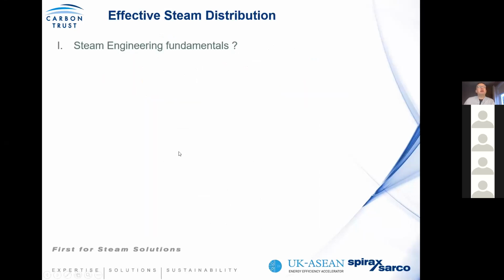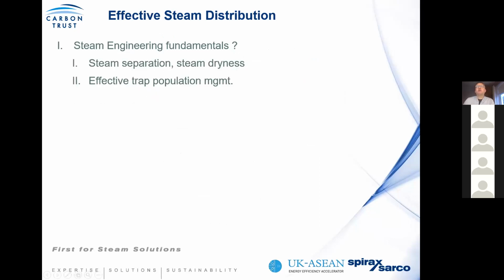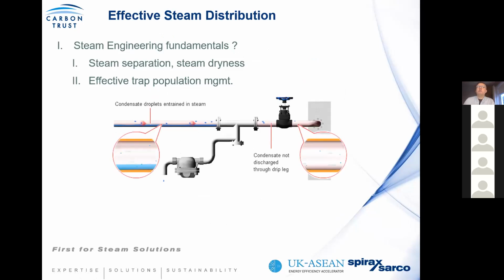So when we start looking at steam dryness, what's also important is that we should look at separation, because even within the steam system, as steam moves through the distribution system, it picks up these water droplets because of the velocity of steam in the piping. So what you will have is droplets of water in your steam system. And again, water is an effective insulator. So as these droplets move forward, they create erosion. They basically have an impact on plant reliability and reduce the heat transfer efficiency.